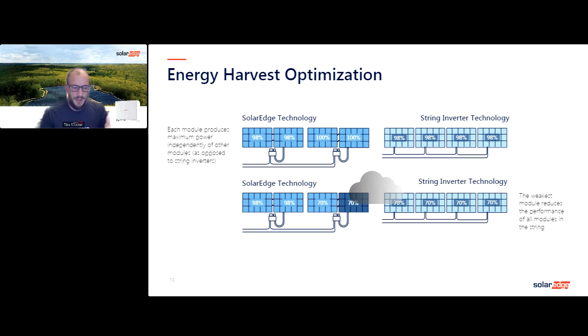And so that mismatch can come in the form of manufacturing tolerance, or thermal mismatch, right? As these modules are ever so slightly pointed in different directions, depending on, again, the slope of the land and the undulating terrain, those will have thermal mismatches. And so obviously the temperature of the module impacts the power performance of each module. You can have different tilt and azimuth, again, due to the challenging terrain that these might be installed on, as well as bifacial modules, right? The albedo of the land behind it, the reflectivity of the land, whether it's snow, grass, could be flowers, those will impact the bifacial gains. And so those also need to be taken into account.